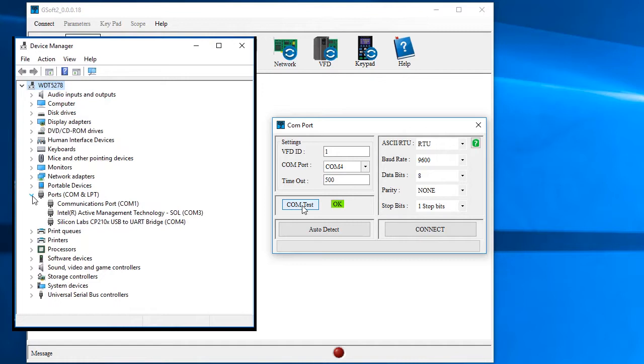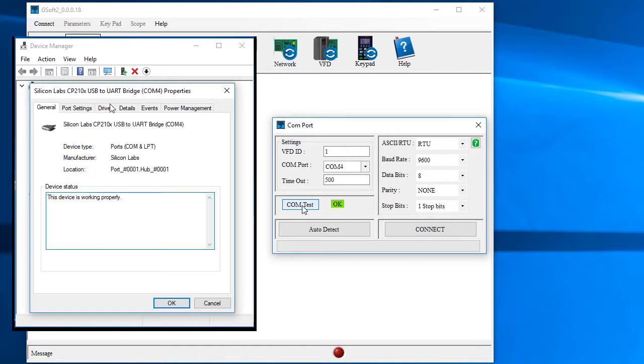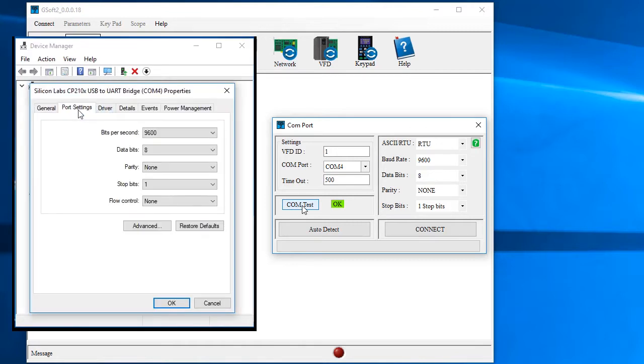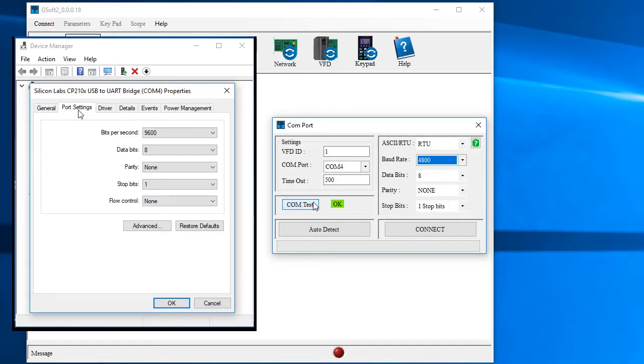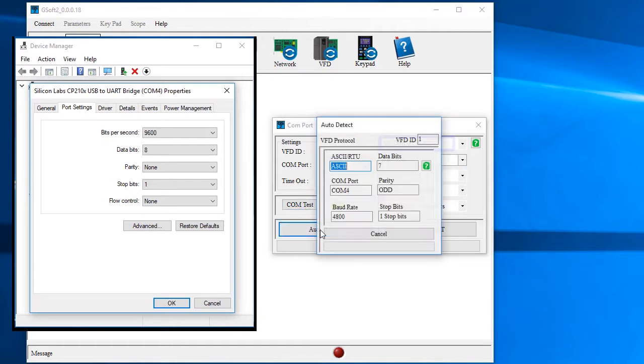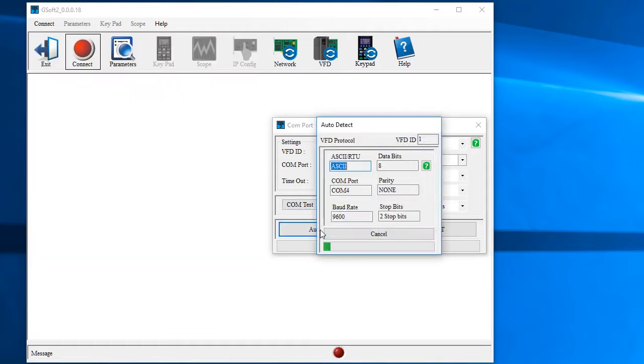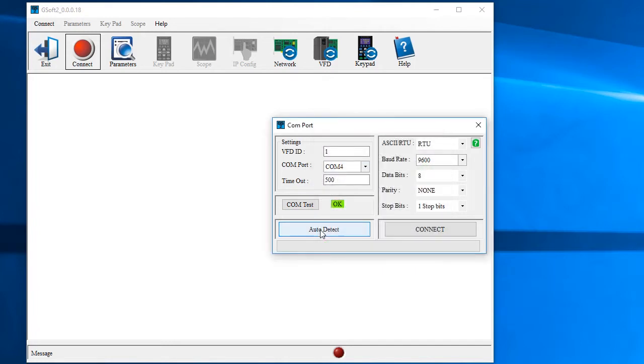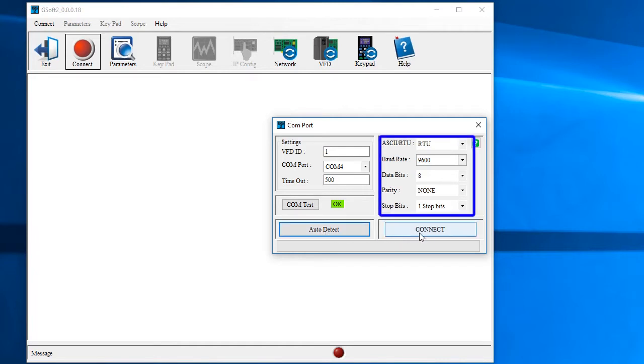If you still get a fault, even if you know you have the correct COM port, then make sure these settings match the COM port settings in the Windows Device Manager and that this is set to RTU. You can also use this auto detect. It tries every combination of every setting so it can take a while. But if you don't remember what baud rate the drive was set to for example, this is a great way to find it. These are the default settings, so always try them first.